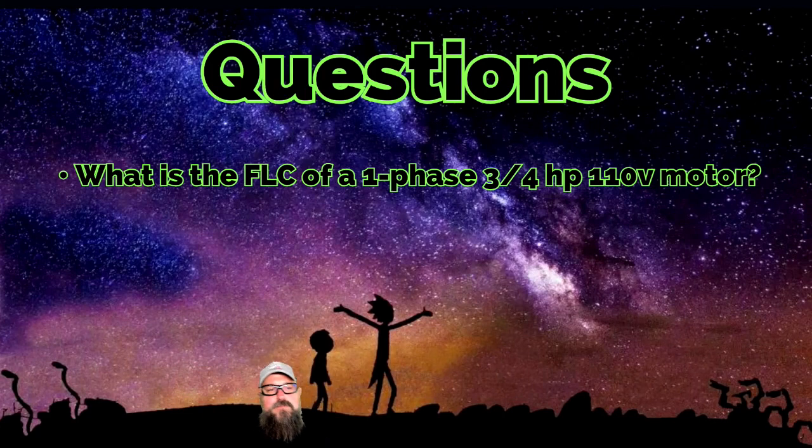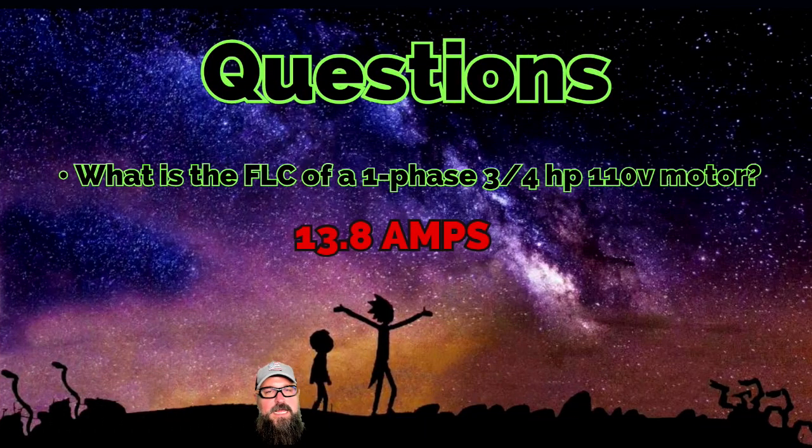Next question. So I'm going to ask this question and let you guys find it. You can pause the video and look the answer up yourself. But here we go. What is the full load current of a single phase, 3/4 horsepower, 110 volt motor? Go ahead and take your time to look up that answer. Pause the video. The answer, 13.8 amps.